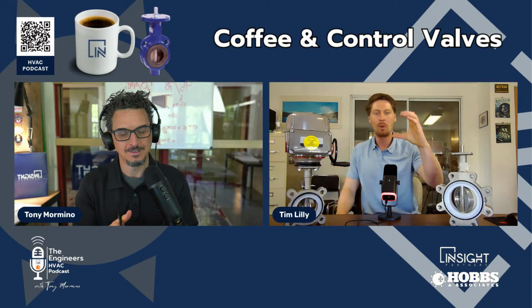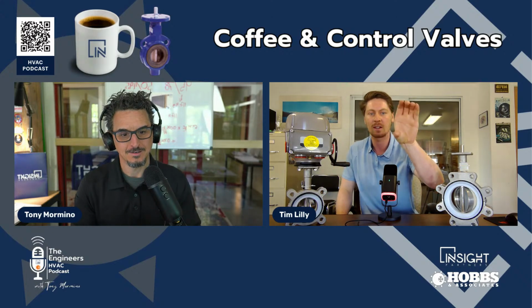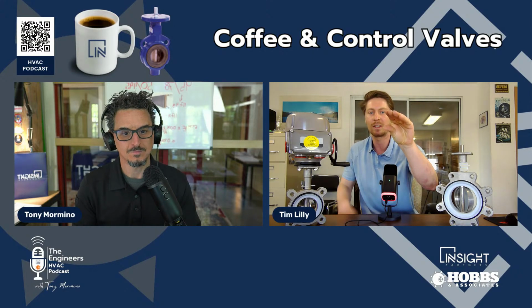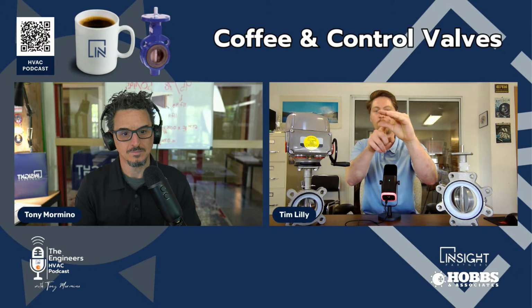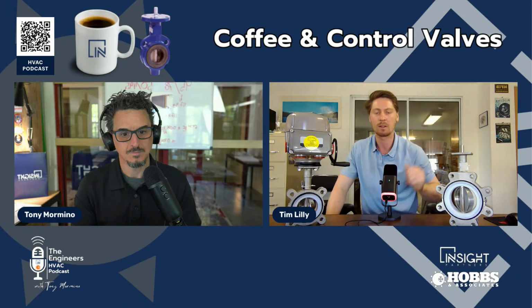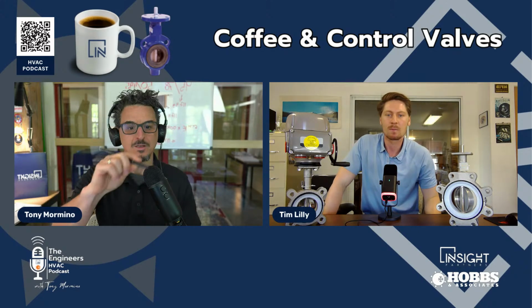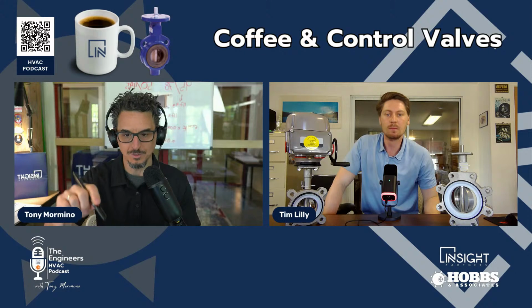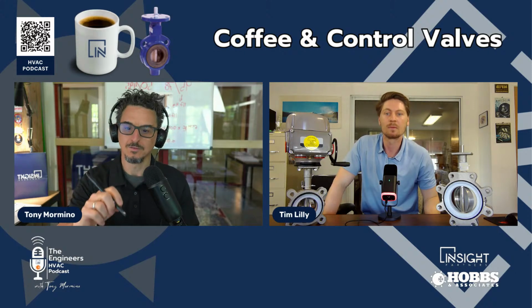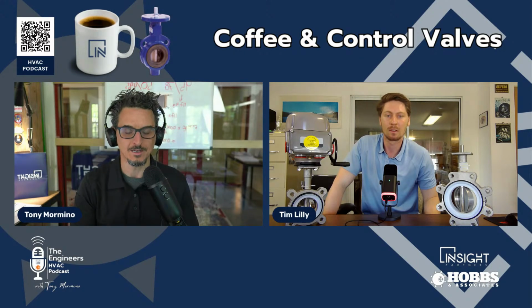So if you think of your ball valve and you have your normal opening like this and it moves like this, your characterized ball valve's opening is going to look more like this. And so when you move, it's slitted and it controls how much water can get through that passageway. So it keeps it even. Yes - in other words, 10% open equals 10% flow, 15% open, it moves along that flow curve.